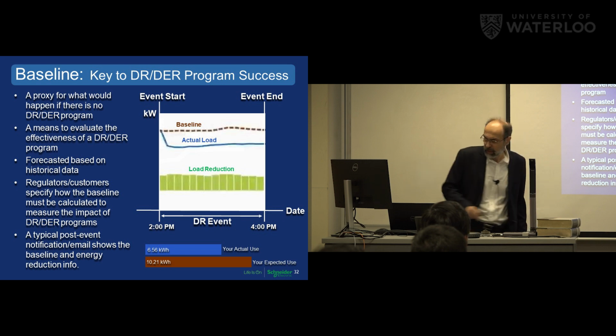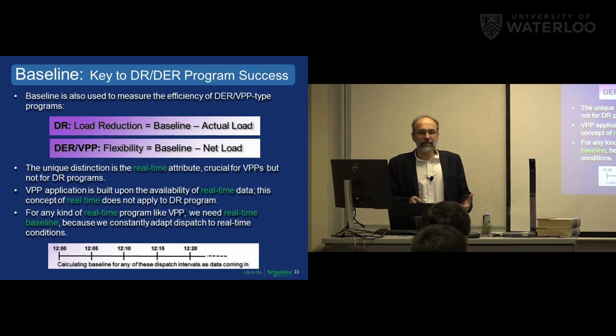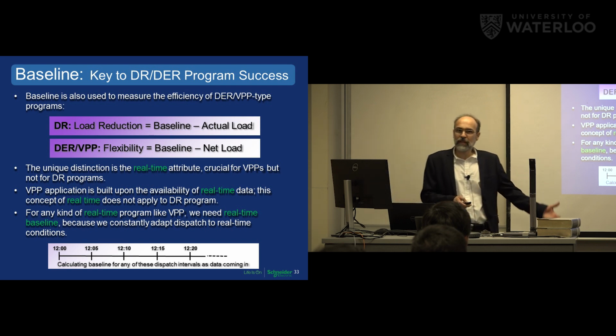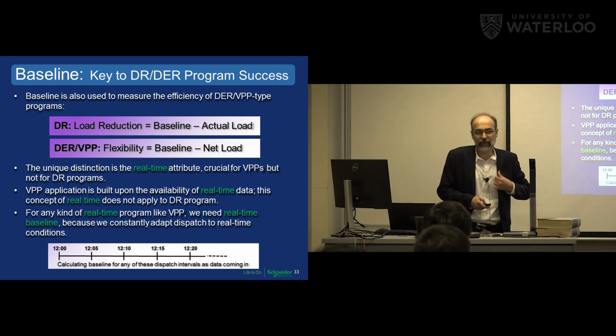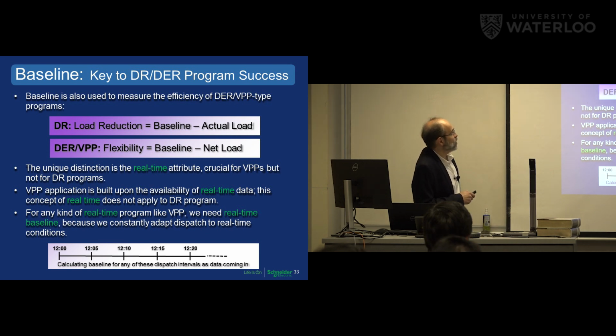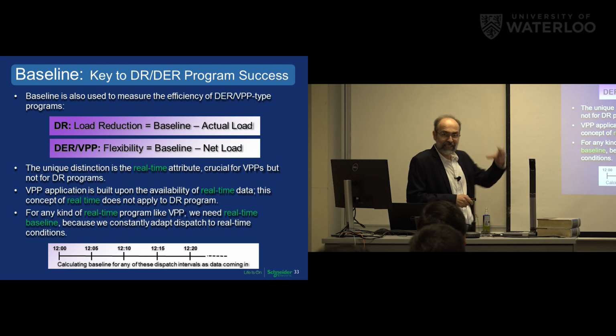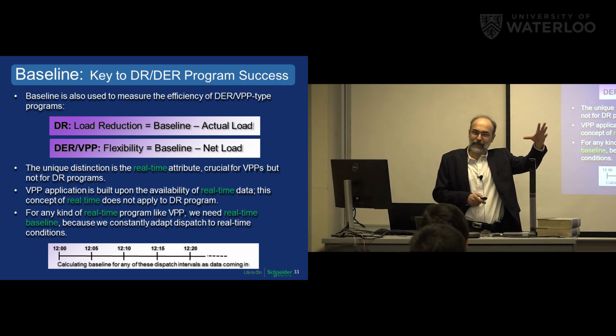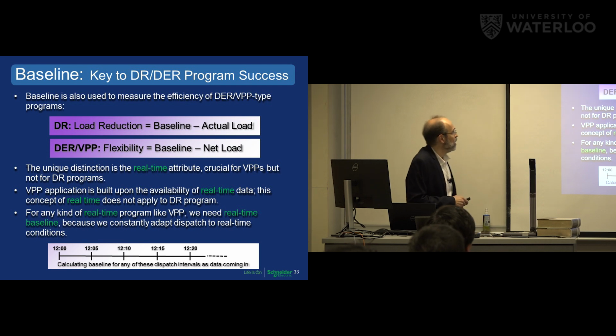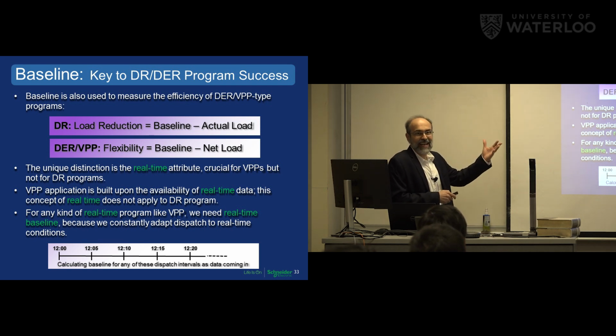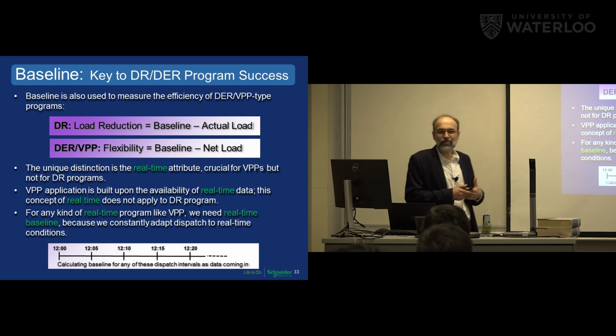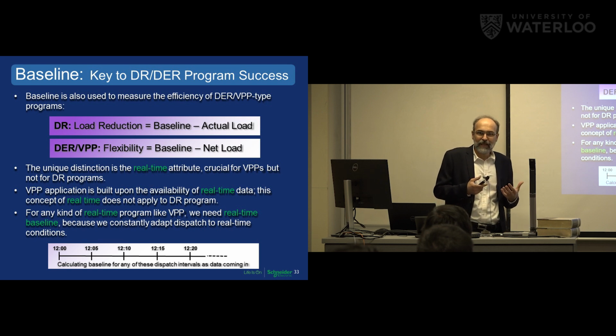This is for demand response, but a similar concept applies to the DER or VPP program. For demand response, load reduction is baseline minus actual load. For the VPP or DER program, it's baseline minus net load, which is the value measured by the smart meter at the service point. The distinction is that for DER/VPP we have real-time data, since VPP is built on the concept of real-time data, but demand response is not like that.